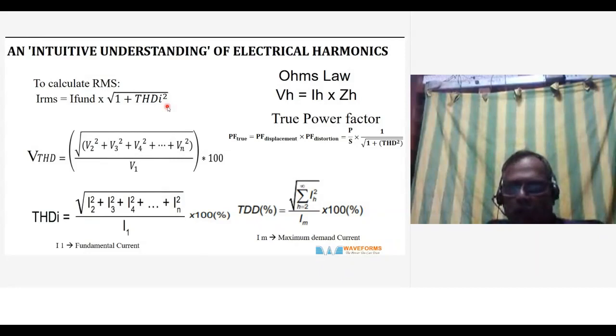So the true power factor is, there are two power factors. When you say true power factor, it means two things. One is the displacement power factor. This normally you'll find in inductive loads. In a purely inductive load and passive load, it will be just displacement power factor. But because of the introduction of automation and power electronics, distortion is introduced. So you have distortion power factor also. So the formula is displacement power factor times distortion power factor. So actual power divided by apparent power, times 1 divided by the square root of 1 plus THD squared. So this is the calculation for the true power factor. So sometimes when you have distortion, capacitor banks do not really work at all. I'll come to that subject later.